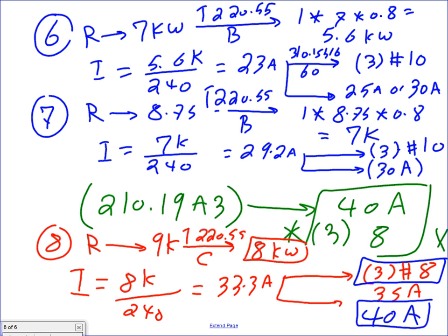Okay, can I move to 9? And you guys can get the rhythm of it. So it keeps going the same rhythm. Let me ask you guys, for item number 8, how many ranges do I have of this size? I have 7. So I will have 7 circuit breakers, 2 pole each, 40 amp. We'll count how many circuit breakers we're going to have by the end. It's going to be a big panel to feed all these systems for me. Any question, guys, about number 8?